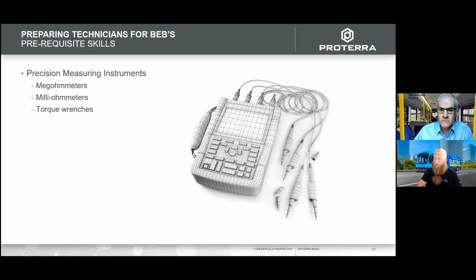Adding to that, torque wrenches and how to properly use them are next. If you over-torque any of these bus bars, that will increase the resistance value as well. So this is actually a great way for you to use that milliohmmeter to confirm that your torque wrench was properly calibrated, and that you've recently calibrated it, and on top of that, that the torque value you used was correct. So it's basically mixing the two of these to confirm your repair.